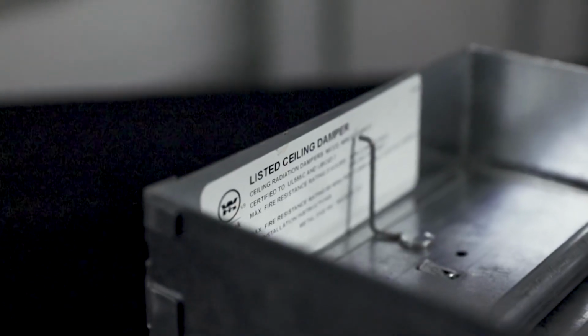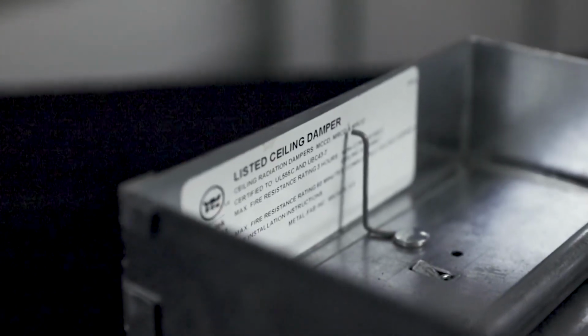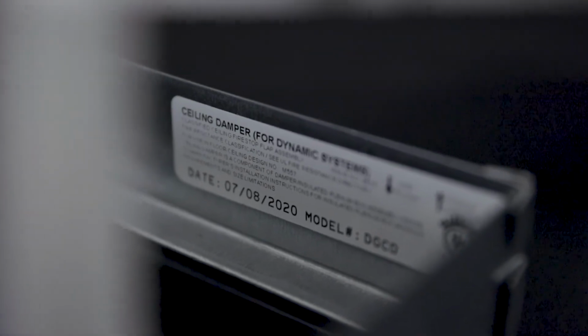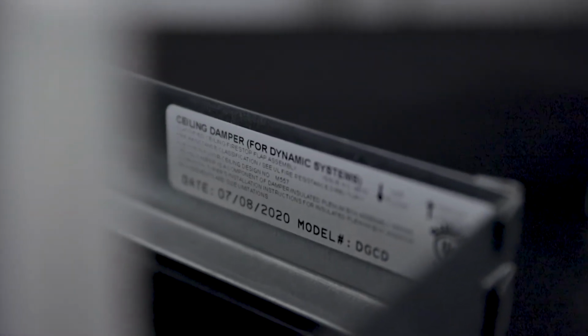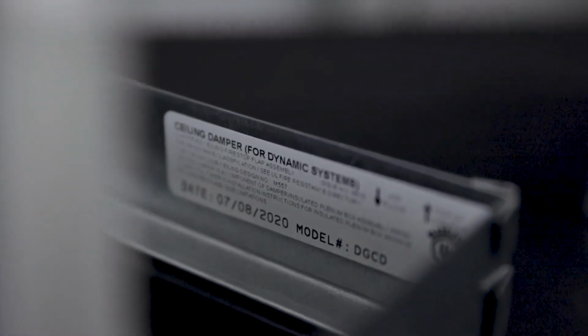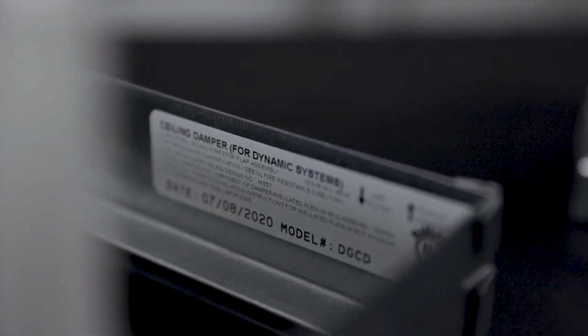Now, as far as inspectors, what makes this easy for inspectors is the labels. So we're going to show you some examples of labels. We have our standard labels for the lay-in type ceilings, then we have the hard ceiling labels. They show the HC dampers, and then we have the DynaGuard dynamic. So when the inspector sees those, that they're listed to UL's requirement for dynamic dampers, then we're good to go.